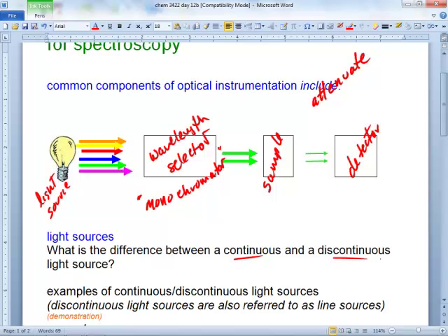It's kind of like this. See, it has all these wavelengths, right? And all that clicking and stuff you're hearing in the UV-vis is for this wavelength selector to select a particular wavelength. There's a lot of rotating gears and all that. We'll talk about the monochromator. But this is an example of a continuous light source. It's just a big smear, Roy G. Biv, right?